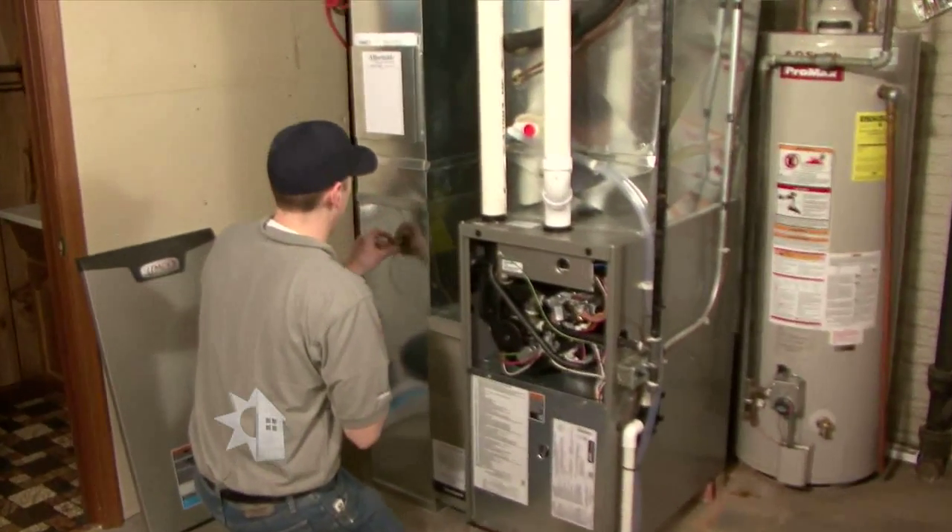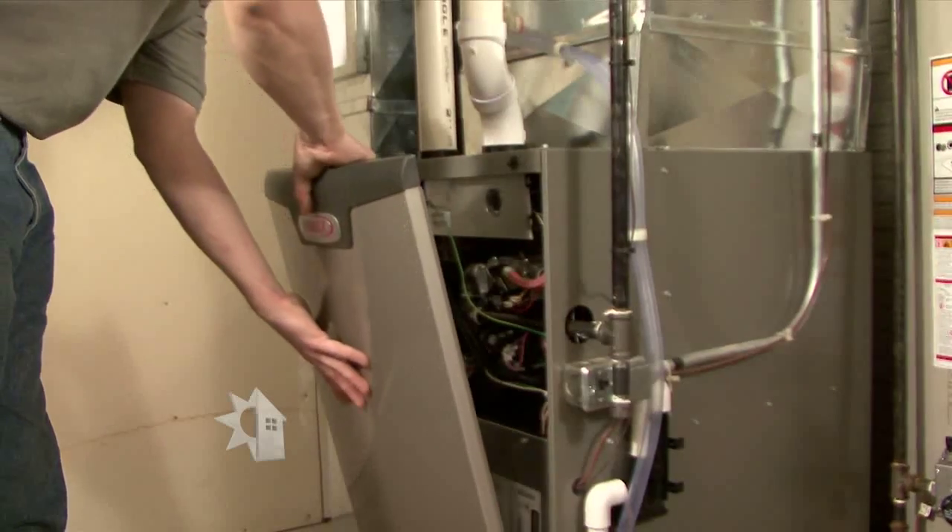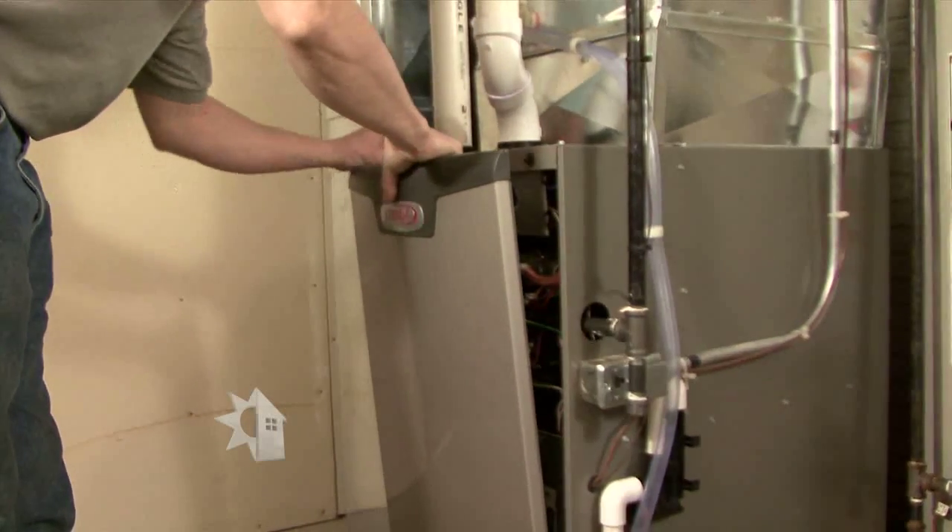They'll go out to your meter and clock the gas consumption on the furnace. They'll stick that into a software program, and that'll spit out a result. If that result is above a certain acceptable level, then it's considered a pass. If not, they'll come back down here and tune it within the manufacturer's specifications, get it up to standard, and eventually it'll be a good install.